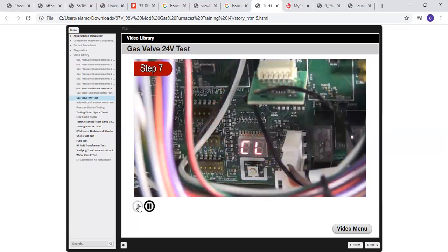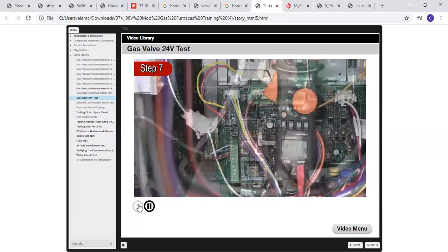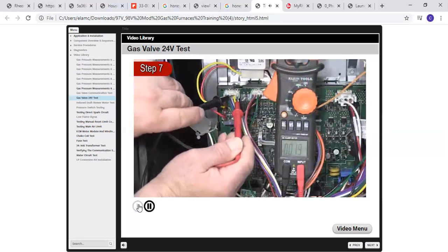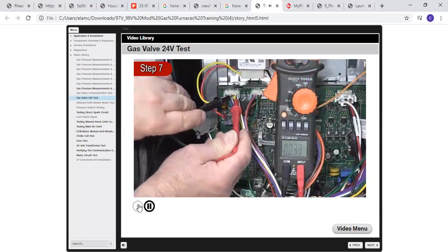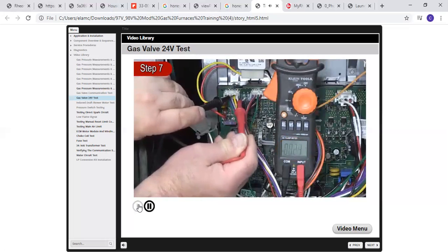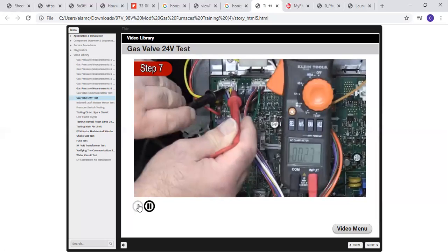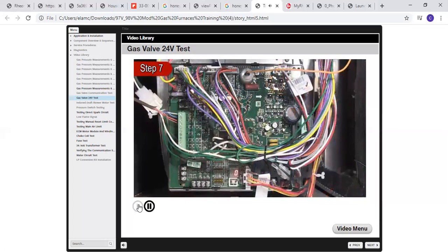Once the retry cycle energizes the direct spark igniter, check for 24 volts at the integrated control plug P7, pins 5 to 4. 24 volts should be present. If voltage is present, the problem is a loose connection between the integrated control board and the gas valve. If voltage is not present, replace the furnace control board.